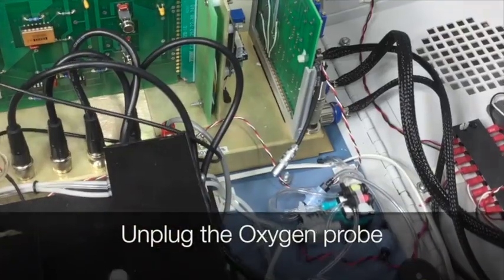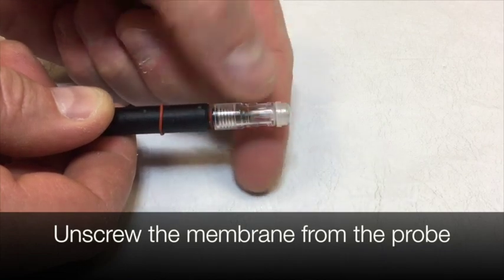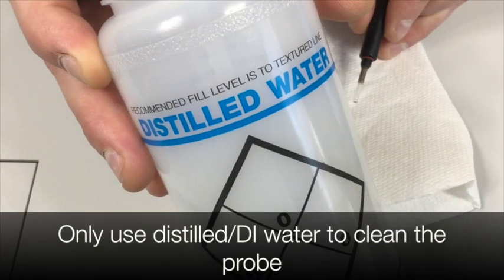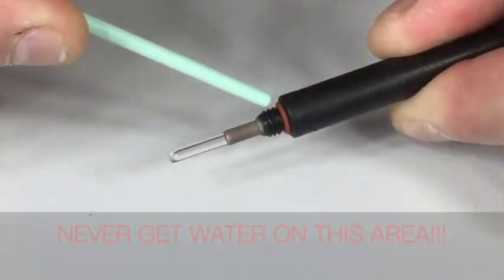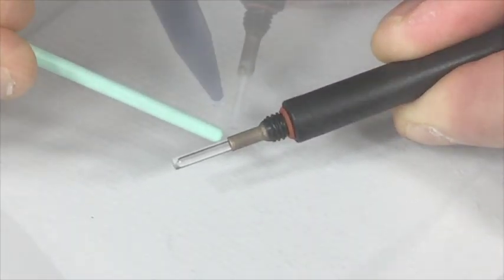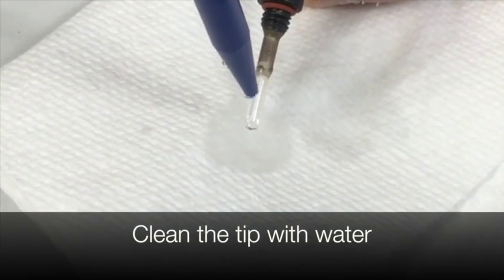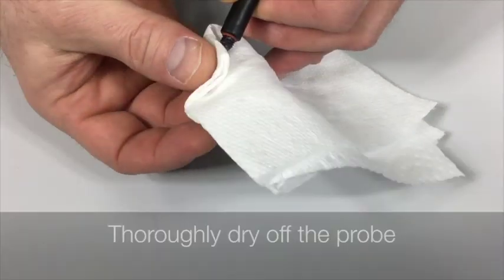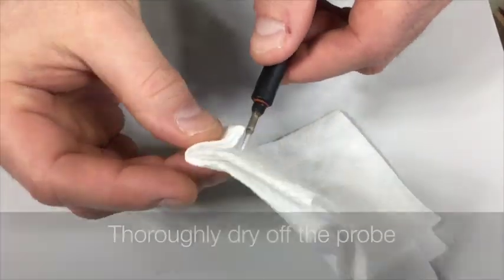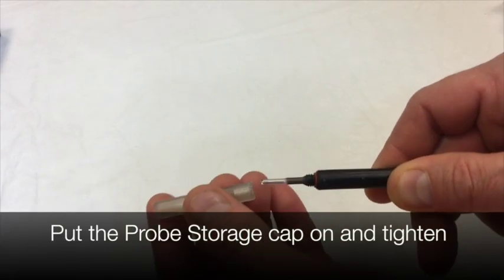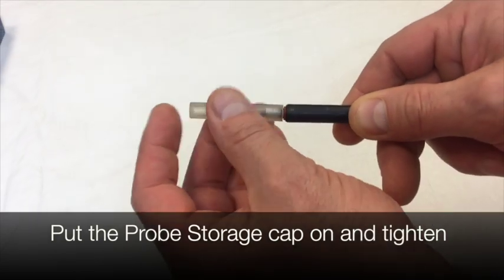First, unplug the oxygen probe. Unscrew the membrane from the probe. Only use distilled or DI water to clean the probe. Never get water in this area. Clean the tip with water. Thoroughly dry off the probe. With a dry probe, put the probe storage cap on and tighten.